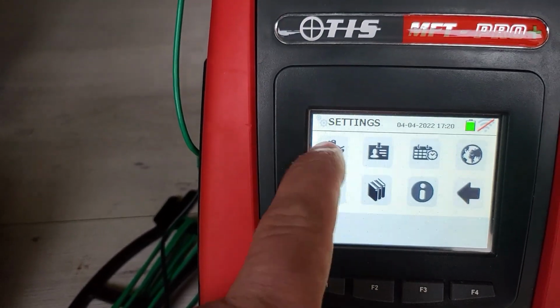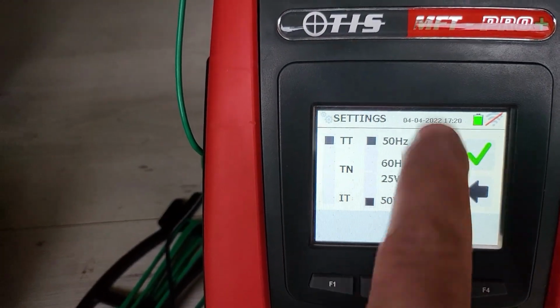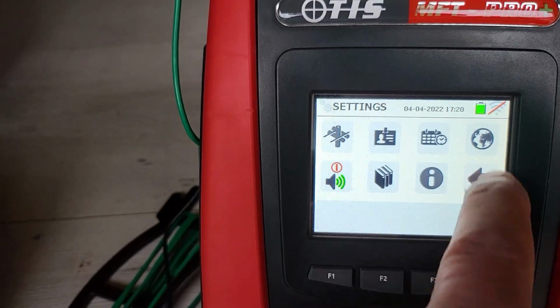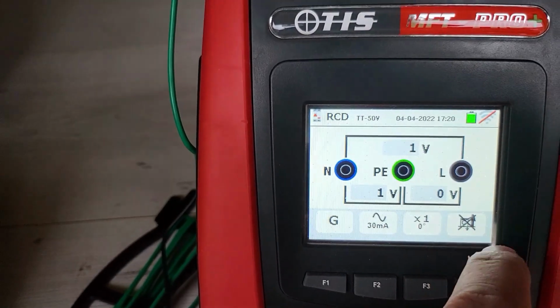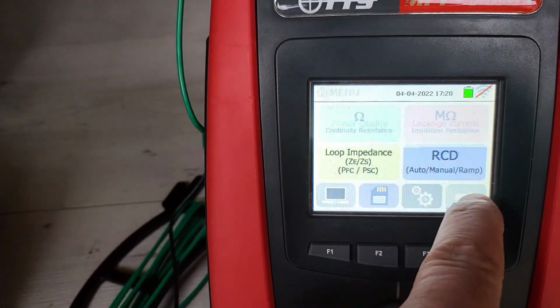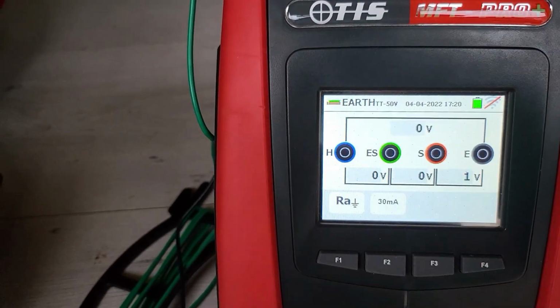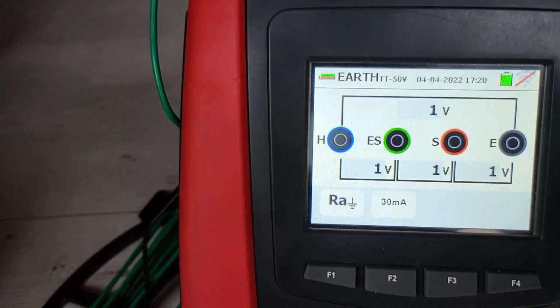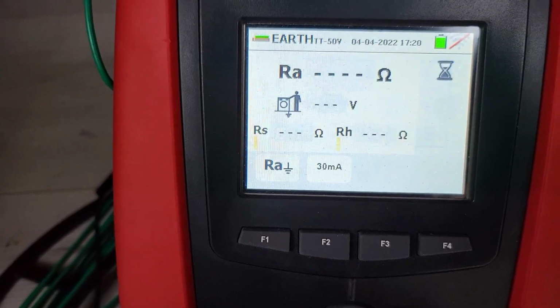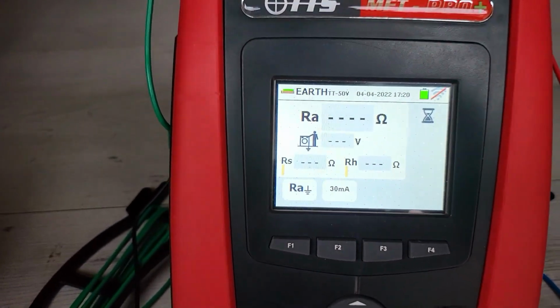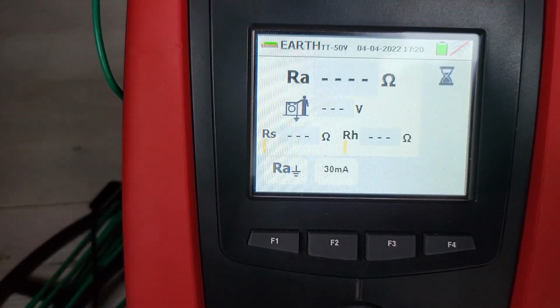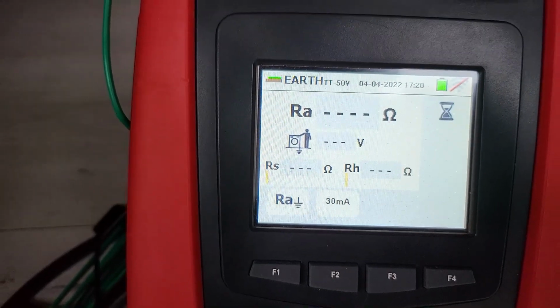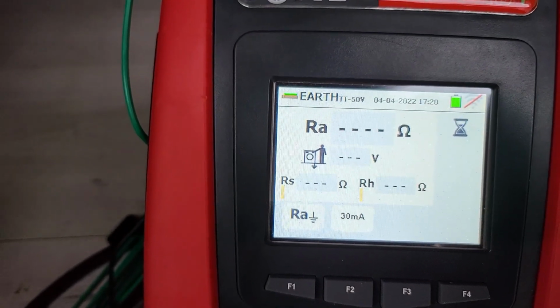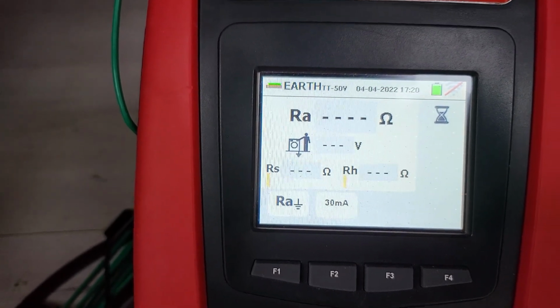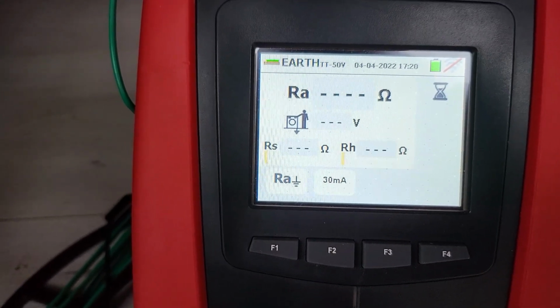So if I go into the settings and I change this over to TT, make sure everything else is set correctly, and we go back into the right test, earth resistance, and you can see here it thinks we've got 30 milliamp RCD protection. If we hit the test now, it'll run through the same process, but it will display the result in a different way. Well, I hope.